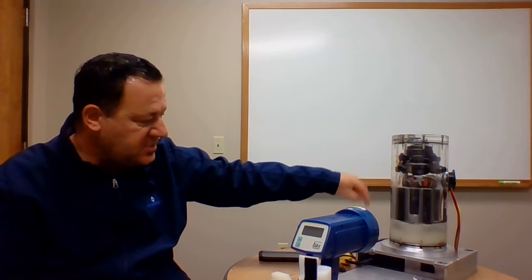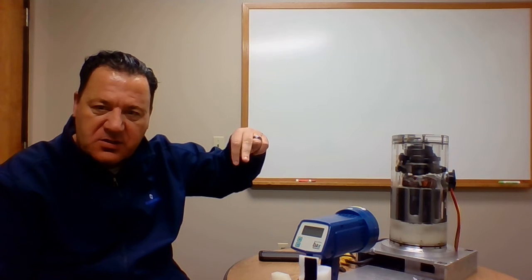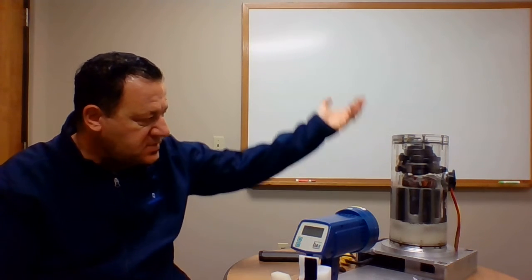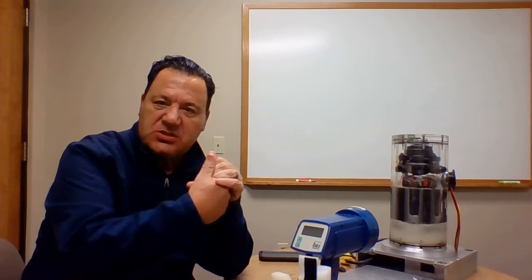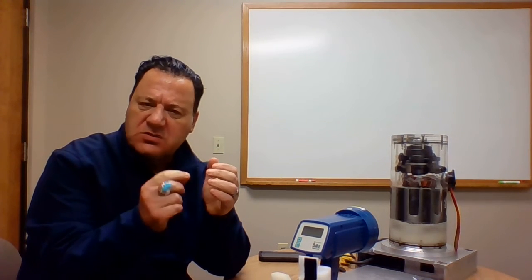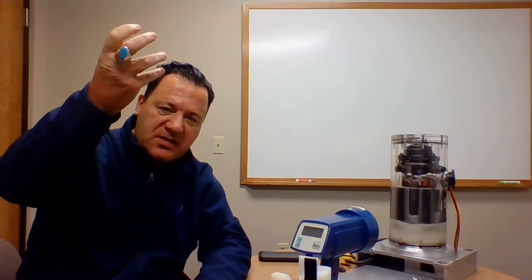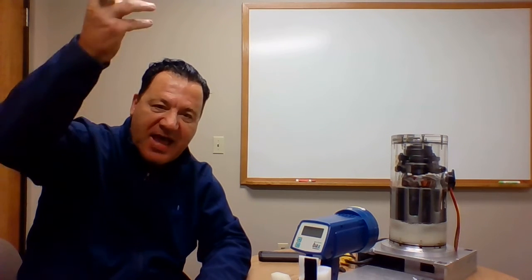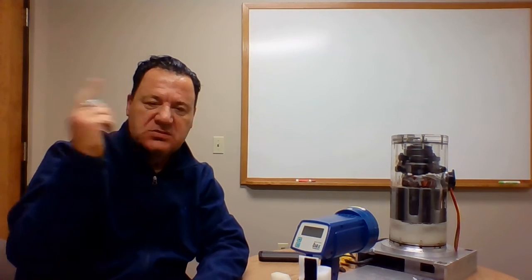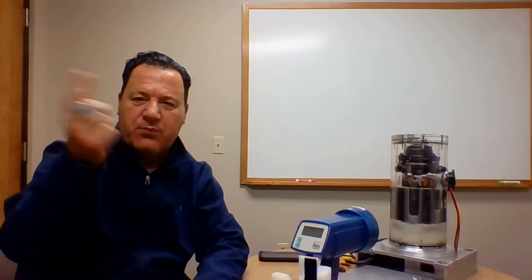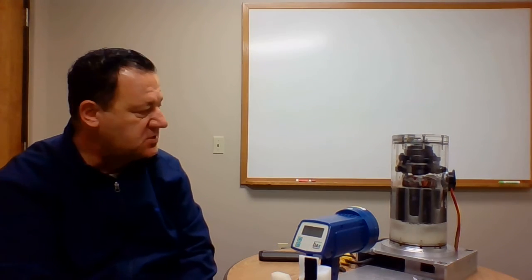That shaft has a little flinger at the bottom of it, almost like a couple of rudders or propellers, causing that oil to come up to the top of it. The shaft is actually drilled out. The hole at the bottom is a little smaller than the hole at the top, causing a vortex effect to come up through that shaft. And it's slightly bored out at a slight angle. So the centrifugal force, almost like a barber pole, allows that oil to come up to the top of the scroll set.